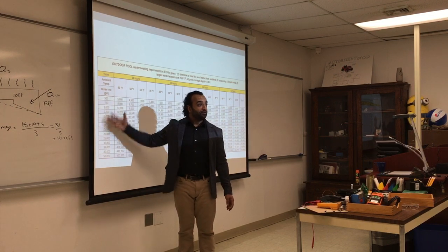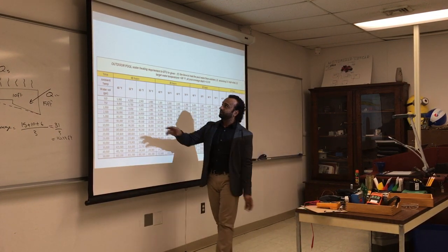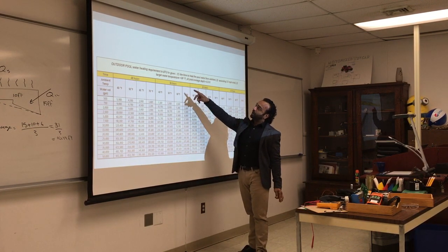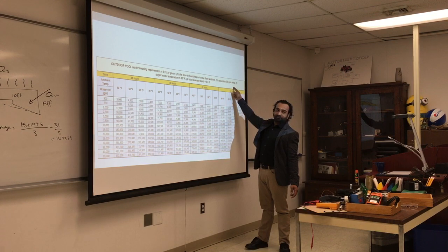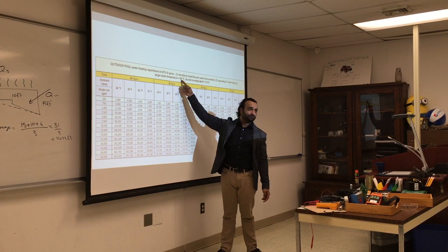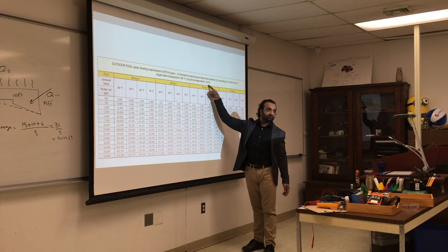So now, it's gonna give you like, how can I say, a sliding ruler to know how long it will take you, how much energy you need to put into a tank. So please just read the fine print. But outdoor pool, water heating requirement in hours, giving the time that you need to heat the pool with, assuming 3.5 miles per hour wind, and target water temperature at 80, which is mostly what people want to heat the pool to, is 80. And pool average depth is 5.5 feet. I had to keep these things constant to be able to vary the other things.